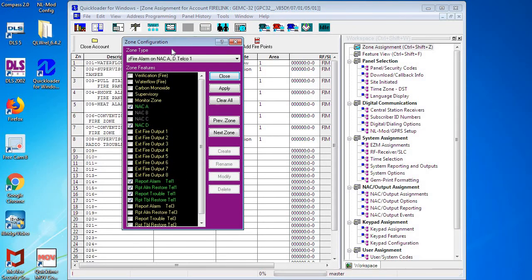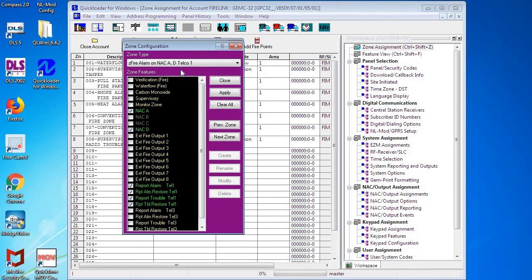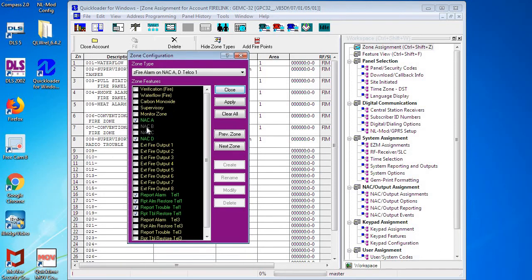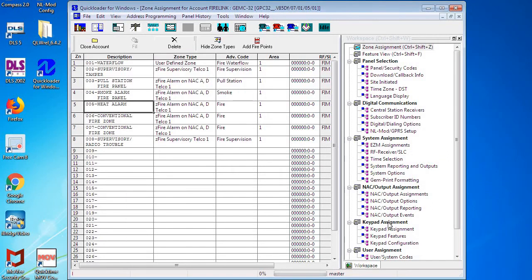Again, this will apply to all the other zones. If you need to change the zone type of something, you click on the zone configuration for that zone and you can change the options for that zone to make it a water flow or supervisory or anything that you needed to.